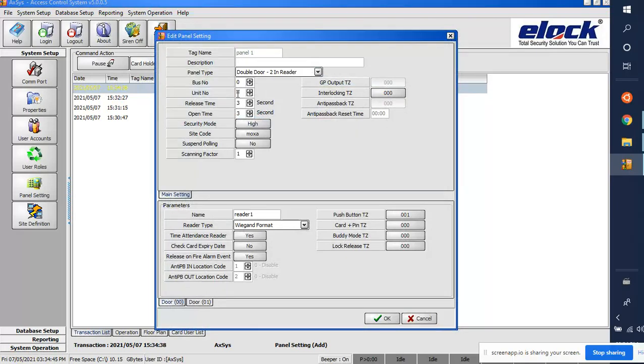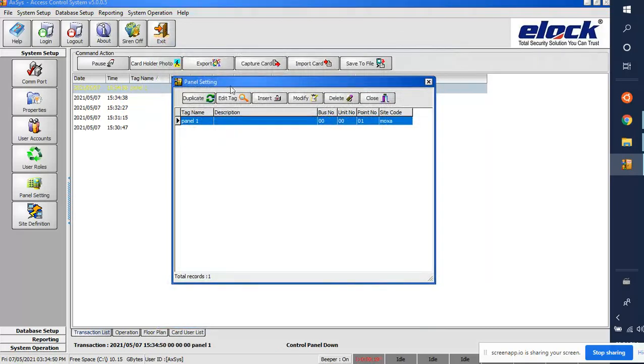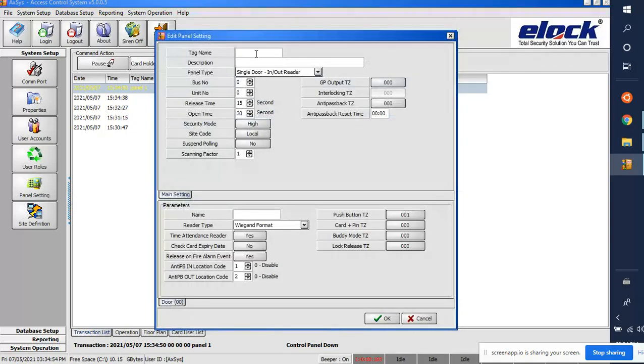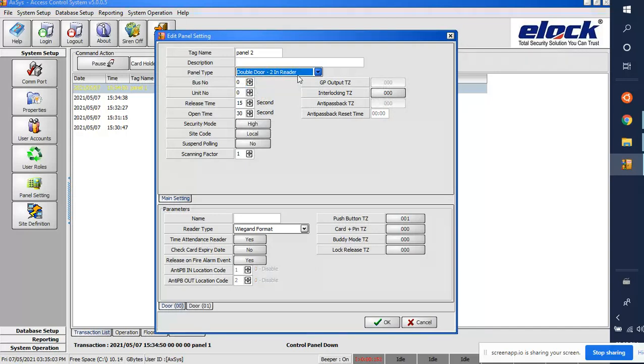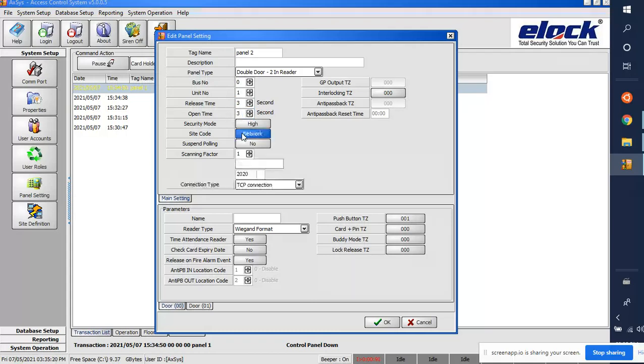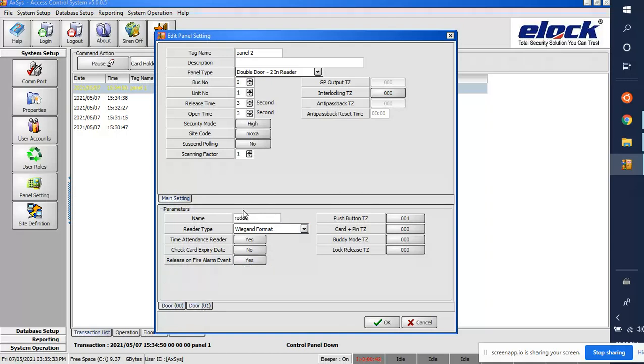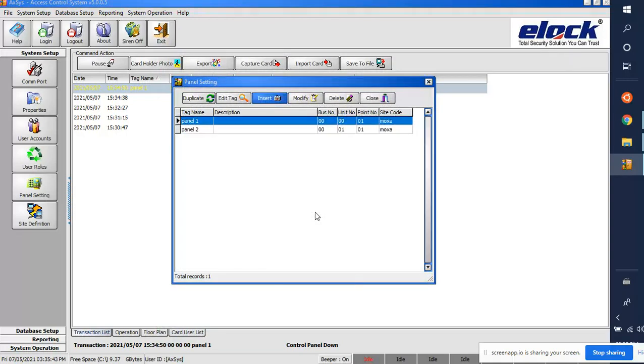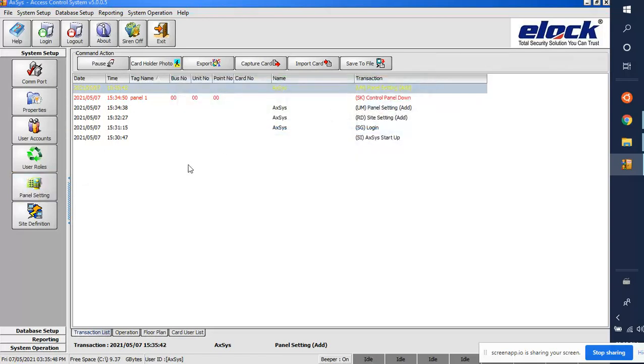Panel 1 is now created with bus number 0 and unit number 0. Now I'll add Panel 2 the same way — Double Door Two-In Reader, bus number 0, unit number 1 (since this is the second panel). Set release and open time to 3 seconds, site code Moxa, and name the readers Reader 3 and Reader 4. Click OK.